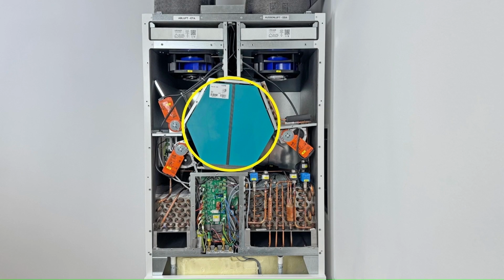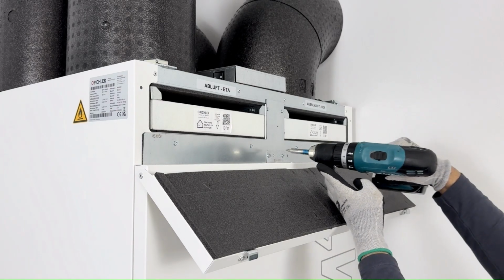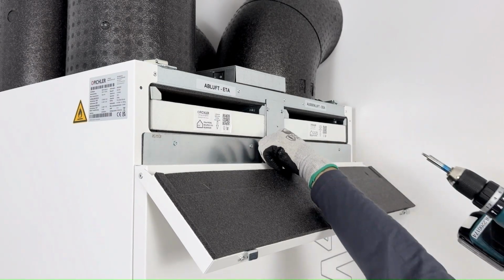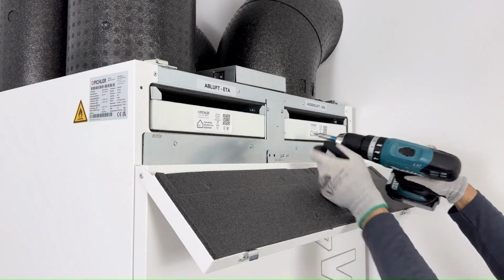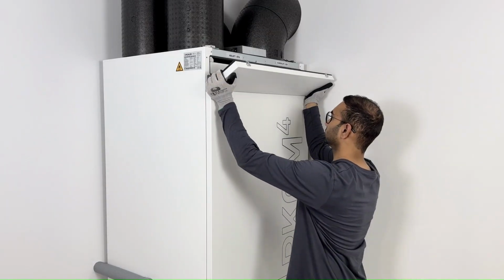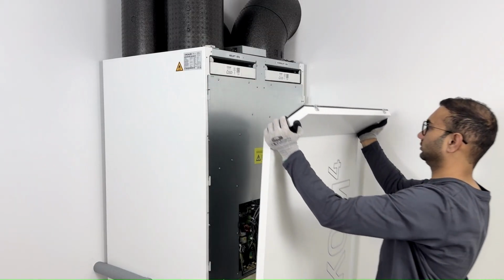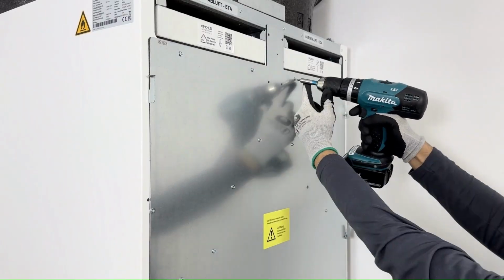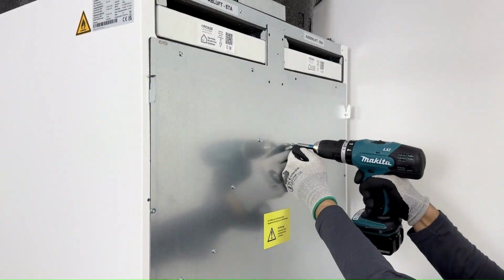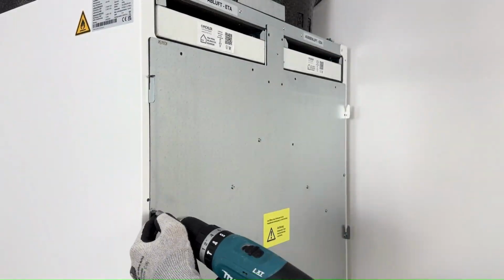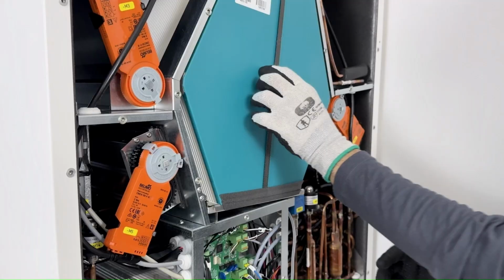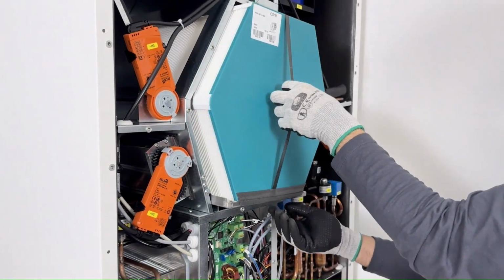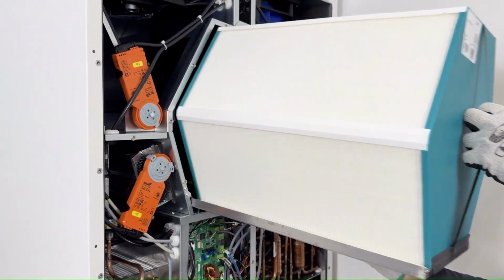After the filter inspection, check and clean the counterflow heat exchanger. For that, loosen the safety screws securing the front hood. Then, remove the front hood by pulling it upwards along with the filter cover. After removing the front cover, carefully loosen all the screws and remove the sealing plate. Carefully extract the counterflow heat exchanger from its bracket using the provided black strap.